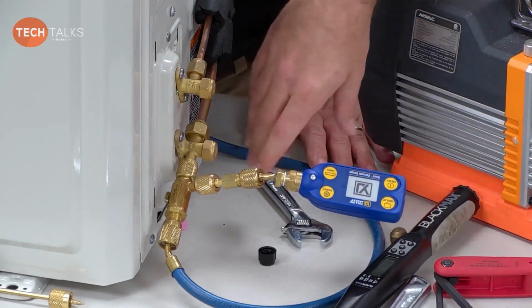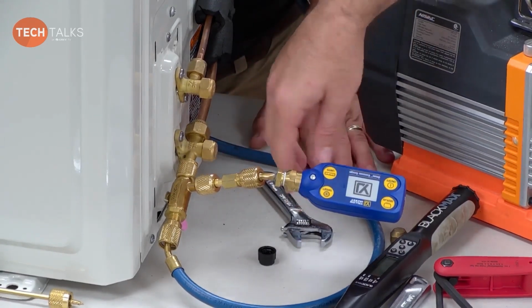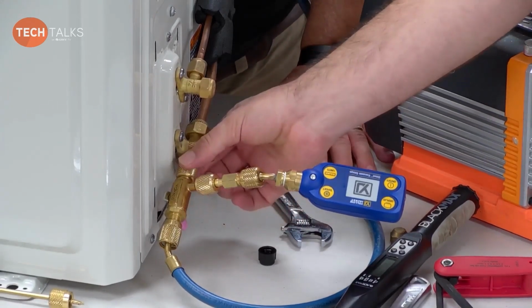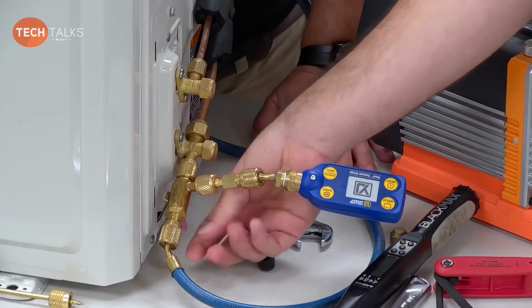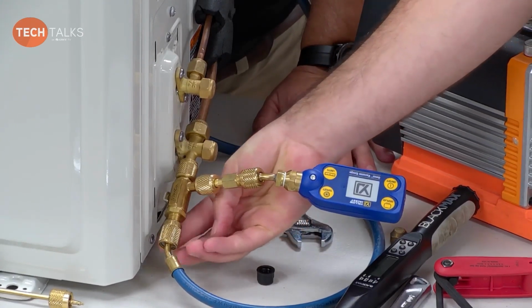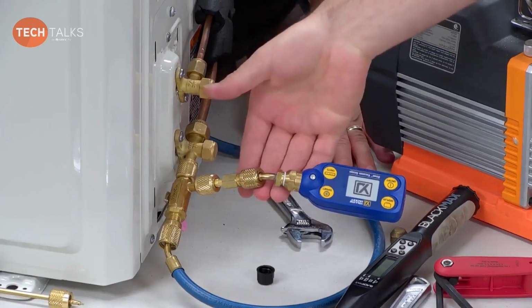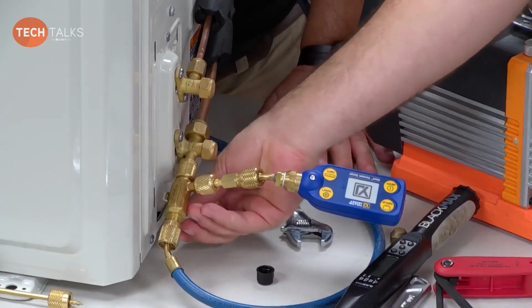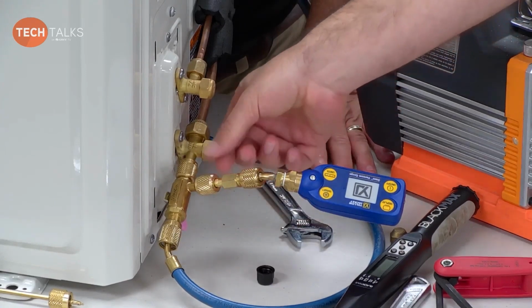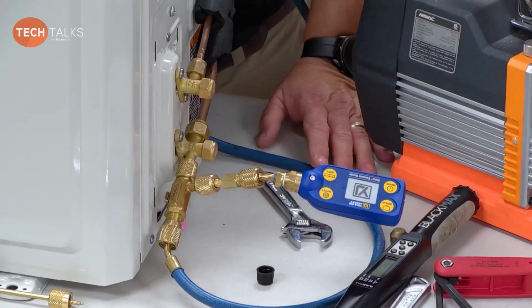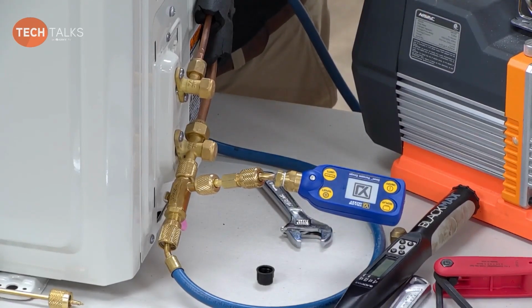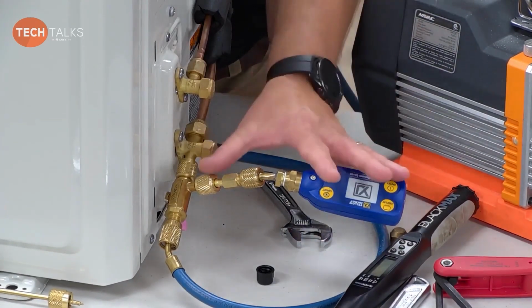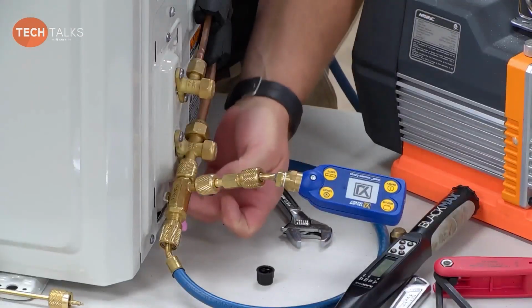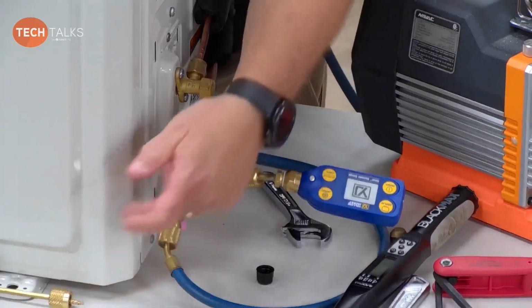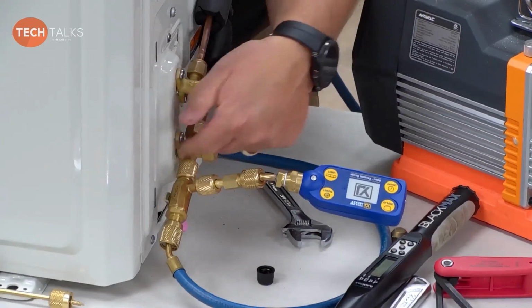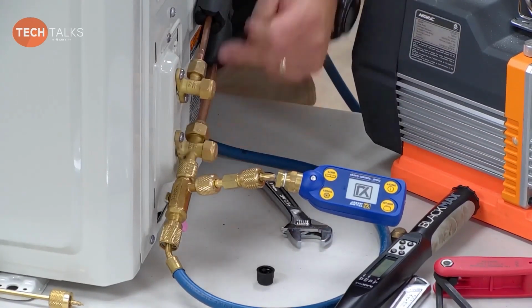So even if you're not using a Schrader core remover, you need some type of valve, whether it be a low loss valve here, so you can shut this off when you turn off your vacuum pump to test your rise. We want to have that valve there so we can lock that off but still read the microns in our line set. So just to recap a little bit, you're set up, you're pulling your vacuum, you're pulling on your micron gauge, this is open, the valve core's out. As you can see laying there on the table, the valve core's already been out. So now we're pulling a vacuum through this, on our lines.